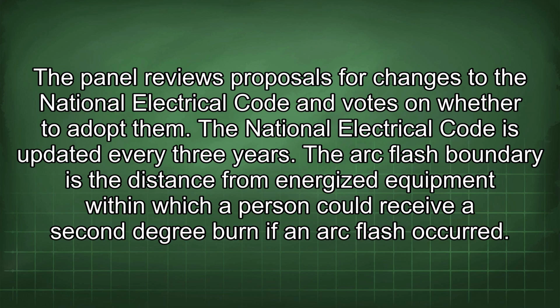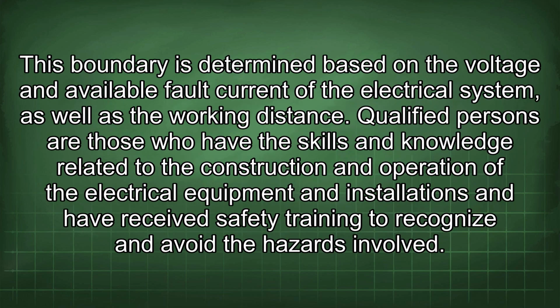The arc flash boundary is the distance from energized equipment within which a person could receive a second-degree burn if an arc flash occurred. This boundary is determined based on the voltage and available fault current of the electrical system, as well as the working distance.